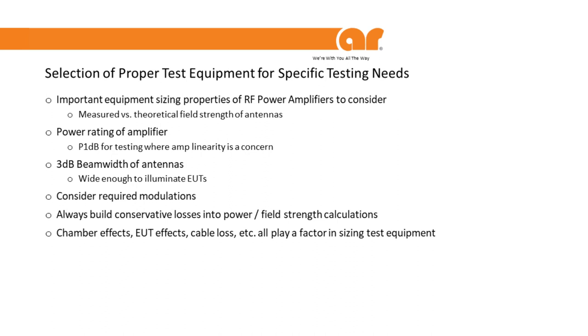If you have a large test sample and a narrow antenna beam width, you will have to run multiple antenna positions to ensure the entire EUT surface is covered during the radiated susceptibility test. Make sure that required modulations — amplitude modulation or pulse modulation, which are common for radiated susceptibility — are supported by your signal generator. If you're not 100% sure prior to the test, connect the signal generator to a spectrum analyzer to verify the modulation meets the standard's requirement.